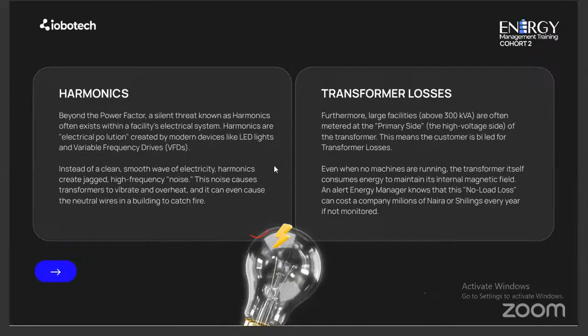Further, large facilities above 300 kVA are often metered on the primary side, the higher voltage side of the transformer. That means the customer is liable for transformer losses. Even when no machines are running, the transformer itself consumes energy to maintain its internal magnetic field. And an alert energy manager knows that these no-load losses can cost a company millions of naira or shillings every year if not monitored.